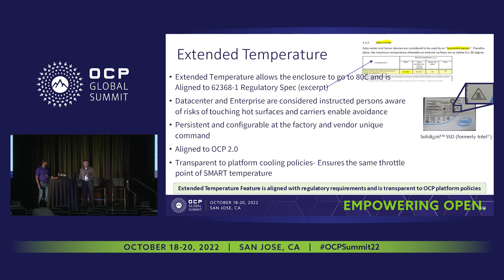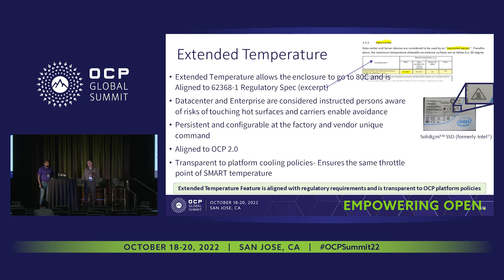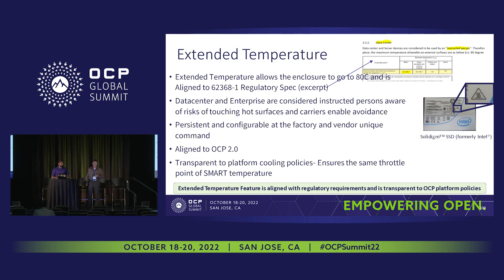The extended temperature feature is aligned to the new regulatory spec. The legacy 70 degrees C requirement was not hazard-based. The new hazard-based one asks what is the likelihood of someone to actually injure themselves. It also takes advantage of the fact that we are talking about instructed or informed people operating the data center. It is configurable at the factory or vendor-unique configurable, and it is aligned to OCP 2.0. The instructional safeguards include the hotspot logo, and we typically will have some indication that says this is a hot surface, do not touch.